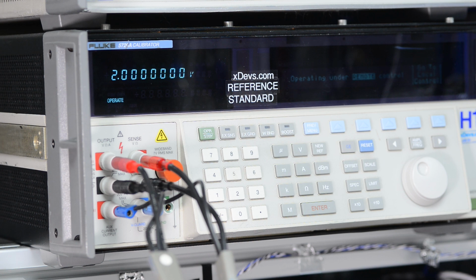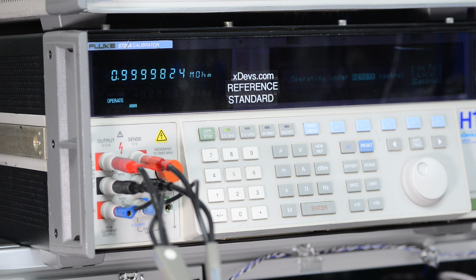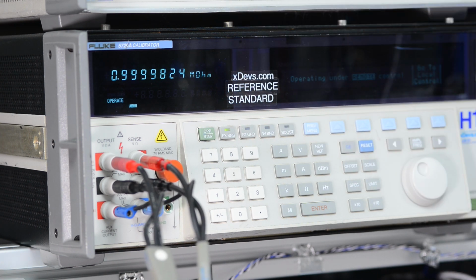Now after 20 volt calibration point, there will be number of resistance ranges to be verified. So for this, 4-wire connection between calibrator and DMM is required. And this is what I'll do in background here. Each calibration step usually takes about 30 to 40 seconds. So here you see me messing with cables to plug everything for the next step.